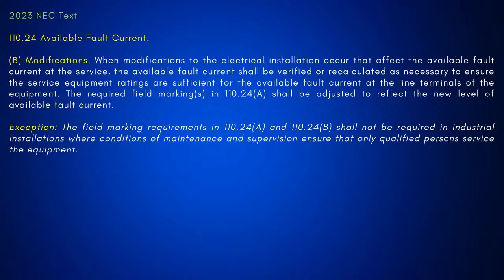Right. But because that would still have to be, you'd still have to calculate, like, let's just say, for example, that one in your thing is a 2000. Let's just say you had a 1000 downstream. You'd still have to have the available fault current at the 1000. Well, sure you would. And then that depends because there's a lot of facilities, they just take the worst case scenario at the service equipment and apply that throughout the plant. But if you're breaking it down inside the plant, well, then you would use the software that helps calculate that cal rating and everything. Okay, gotcha.